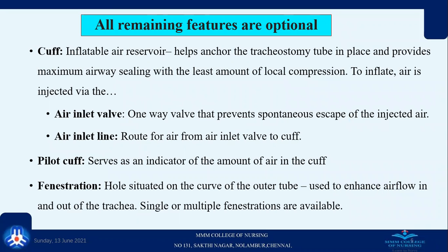All other remaining features are optional. These optional features are cuff. Certain tracheostomy tubes have an inflatable air reservoir, which helps anchor the tracheostomy tube in place and provides maximum airway sealing with the least amount of local compression. To inflate this cuff, air is injected via the air inlet valve. It is a one-way valve that prevents spontaneous escape of the injected air.